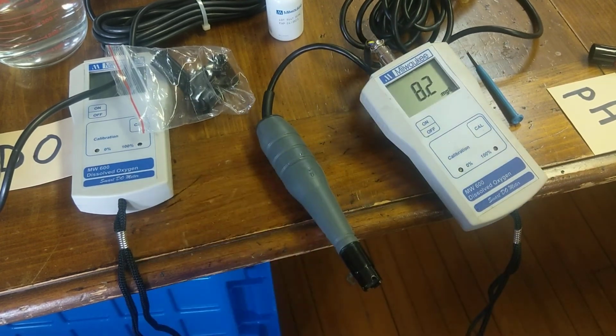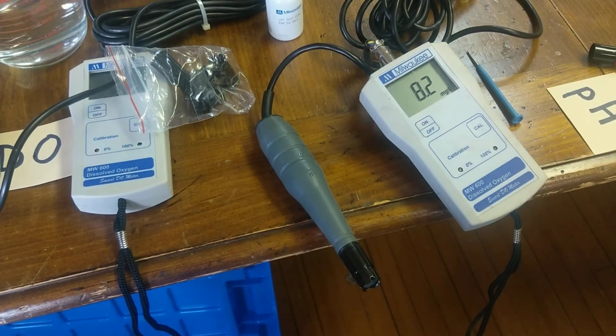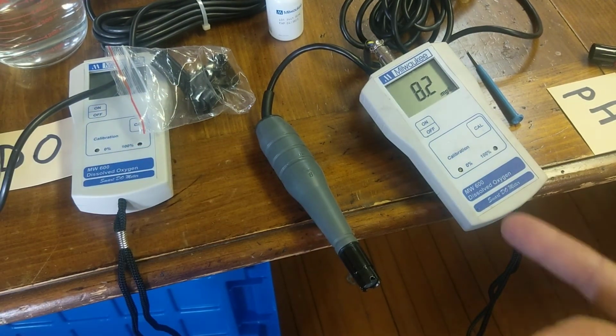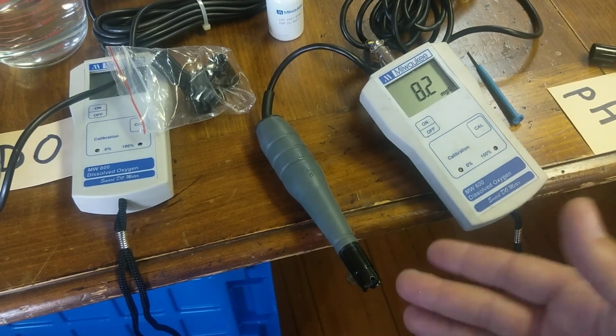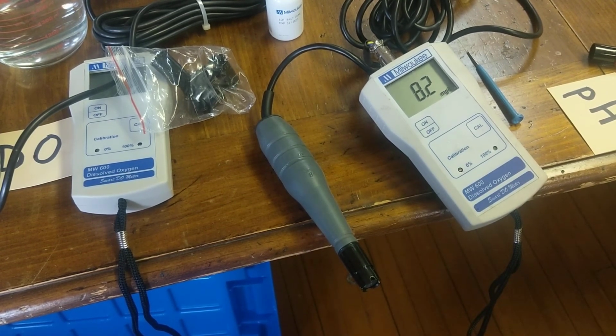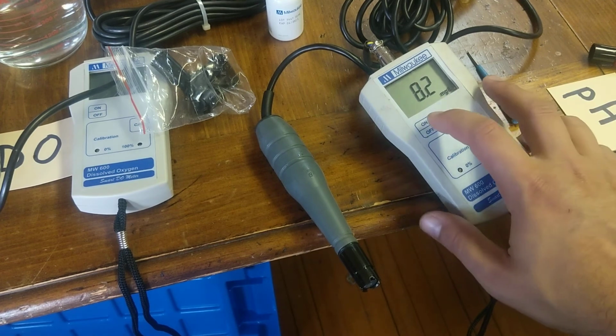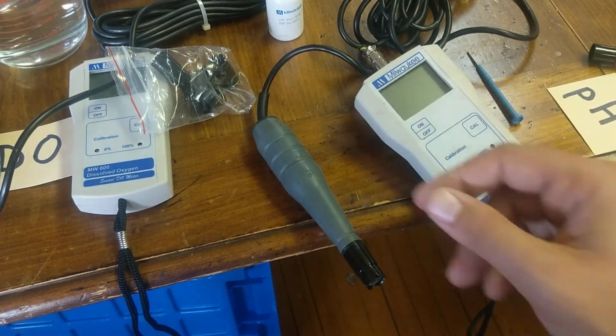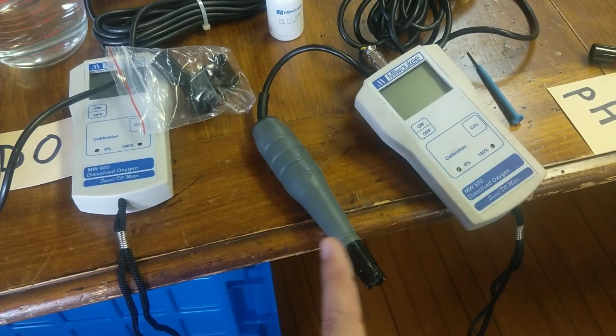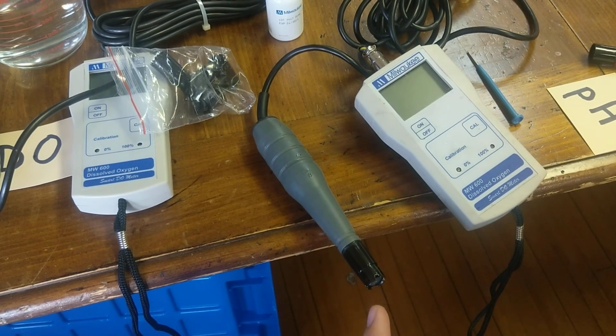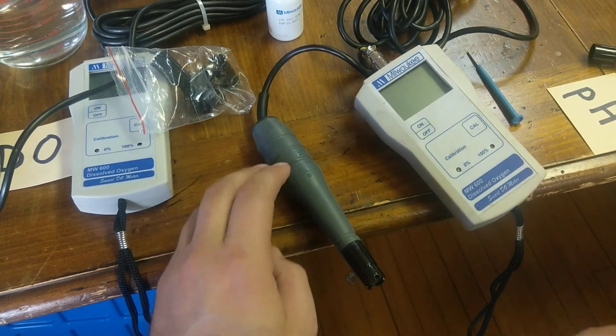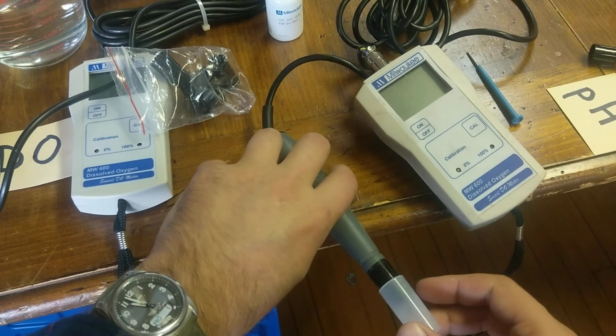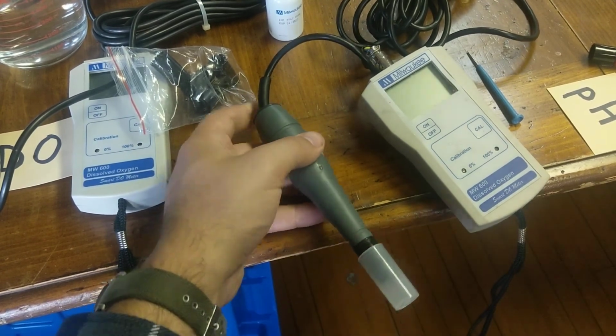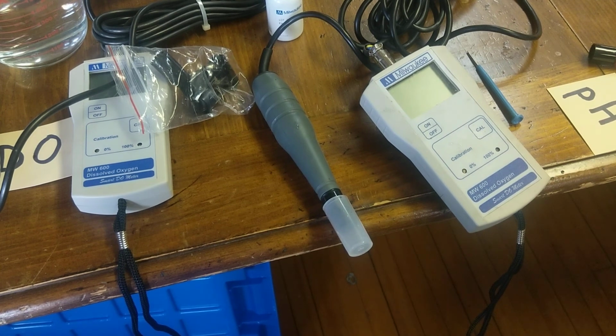Again, alternatively, you can just hang it off the end like so, but the way I was taught was to do it this way. The revised instructions tell you just to hang it off the end and calibrate it like that until the display reads 100. When you're done, just shut it off like so and make sure it's capped. Again, the cap should be dry, the outside should be dry. Don't touch the end of this sensitive sensor over here. Not so good. But if you're going to use it the next day, I will sometimes just cap it wet and leave it like that. Alright, that should be it for dissolved oxygen.